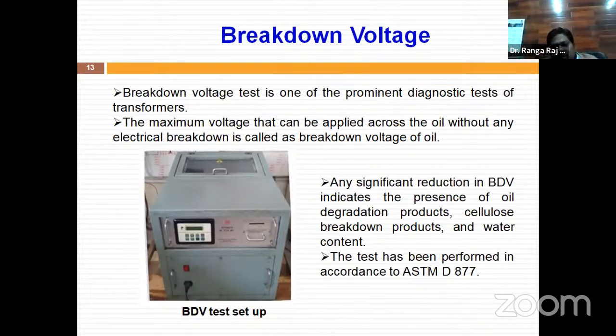At 60 kilovolt, after 20 to 30 years it becomes around 30 to 35 to 40, and after 35 to 40 years it becomes 25 kilovolt. So we need to check it always. We should not leave the oil just like that, because one day you will find the blast, right? So we should know the right health and status of the insulation.